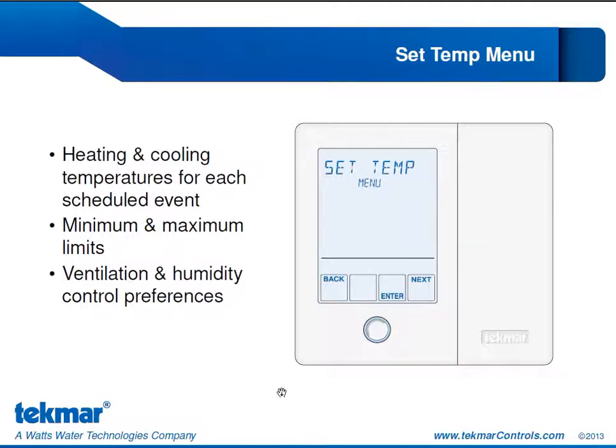The set temp menu is where you program your heating and cooling temperatures for each scheduled event. So here is where we're going to configure the set heat room for the occupied, unoccupied, and away time, the set cool room for the unoccupied, occupied, and away time. It's also where we set up our minimum and maximum limits. So here's where we program our floor min and our floor max for occupied, unoccupied, and away.